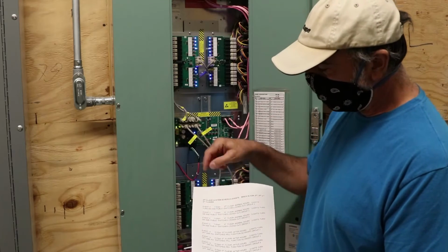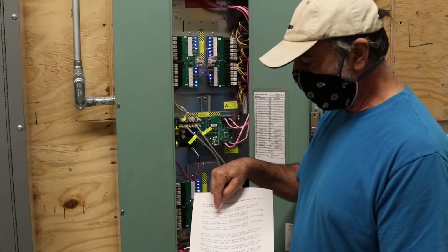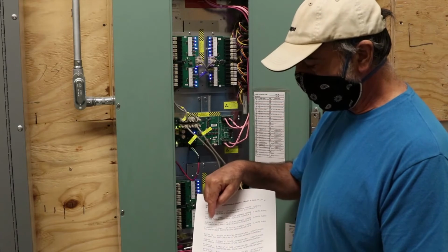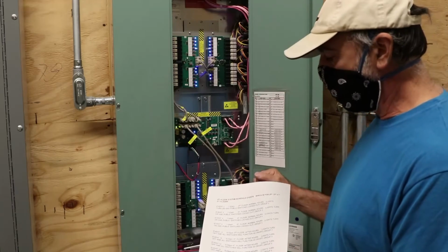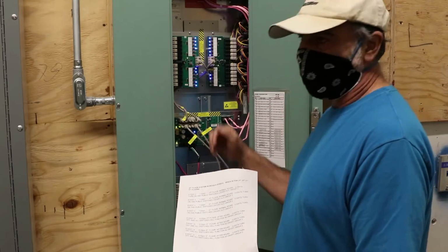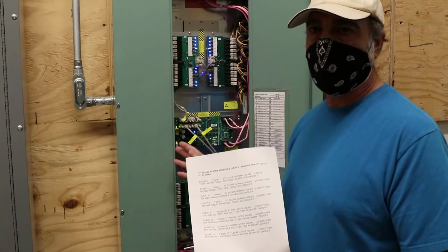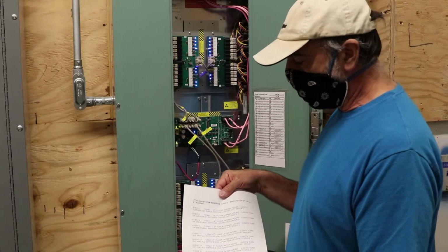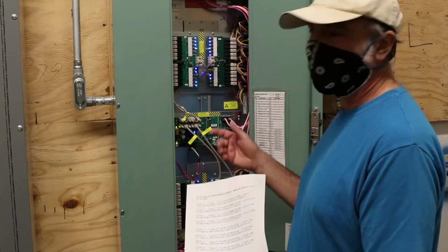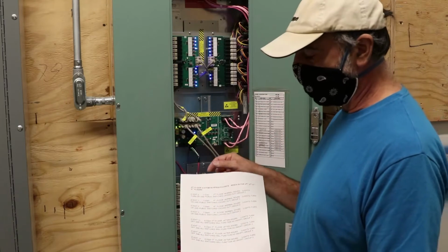The only thing that's different is event 3, which is floor 3, is 7:03, event 4 is 7:04, and event 5 is 7:05, and that's the 4 different floors. I just have them staggered just so there's not an inrush of all the lights turning on at 7 o'clock in the morning. That's the only reason I staggered it. Probably not really necessary with LEDs, but that's how I used to do it, with incandescent lighting in the past.